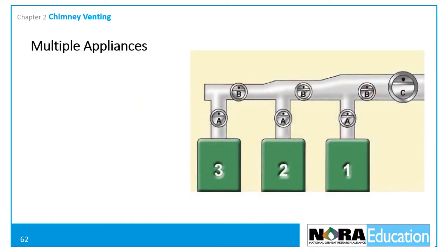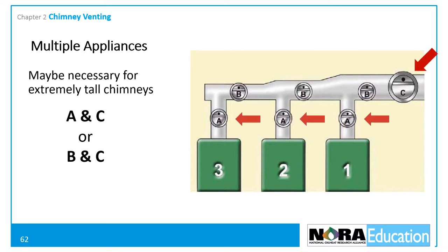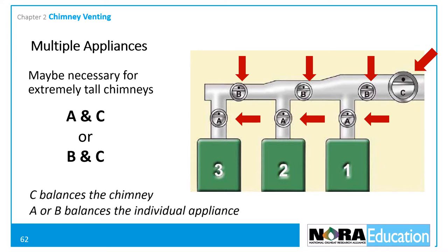Extremely tall chimneys may require multiple draft controls to enable proper draft. In these situations, one control should be installed at location C, and individual controls at either A or B locations. The control at C balances the chimney, and the ones at A or B balance draft for the individual appliances.